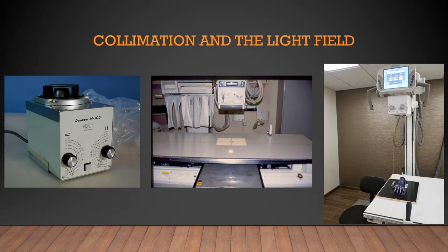When selecting which side of the table the patient is going to be x-rayed on, we want to make sure that the patient is being x-rayed on the side of the table farthest from us as the operator. In this case, the patient is as far away from the console as possible. The light field is the beam of light exiting the x-ray tube, and the operator should consider the light field approximate to the x-ray beam.